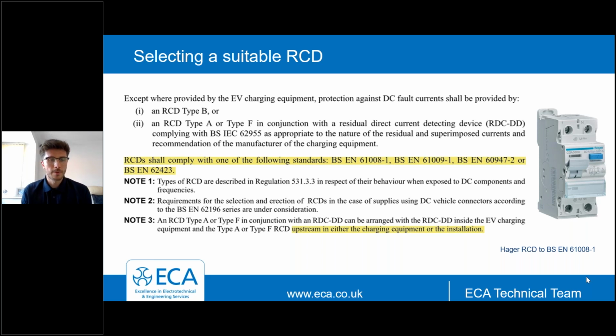Now, some further information around this that provides some further guidance here, and that's in Note 3. Note 3 tells us an RCD of Type A or Type F in conjunction with an RDC-DD can be arranged with the RDC-DD inside the EV charging equipment. So as mentioned earlier, it's quite often these RDC-DD devices are within the EV charging equipment. And then the Type A or Type F RCD upstream, so before there, either in the charging equipment, again, that can be fine if it's a suitable RCD, or within the installation.